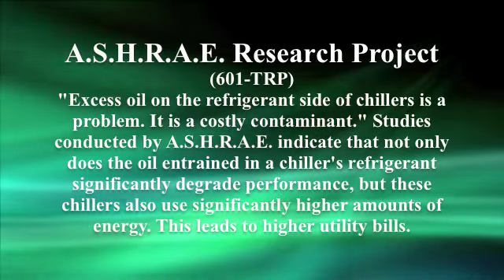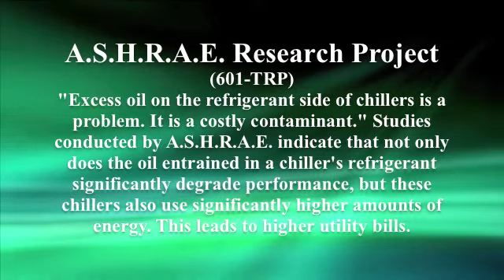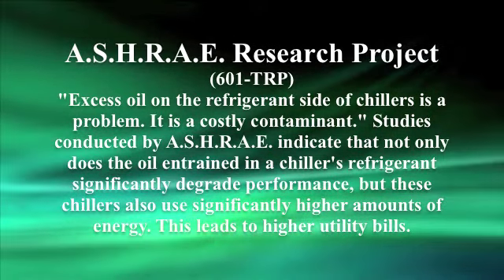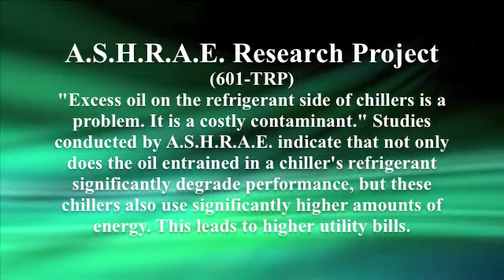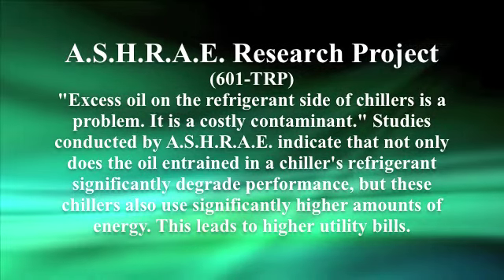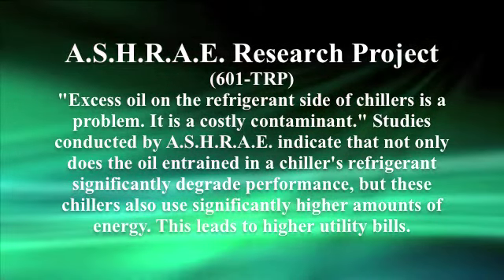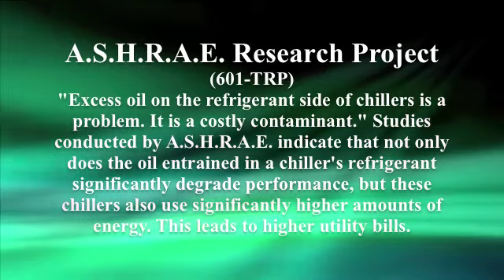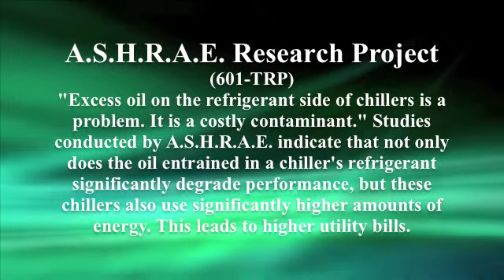Excess oil on the refrigerant side of chillers is a problem. It is a costly contaminant. Studies conducted by ASHRAE indicate that not only does the oil entrained in a chiller's refrigerant significantly degrade performance, but these chillers also use significantly higher amounts of energy. This leads to higher utility bills.